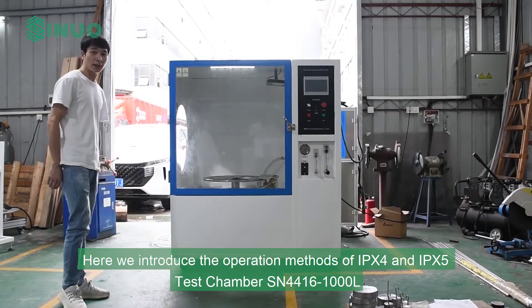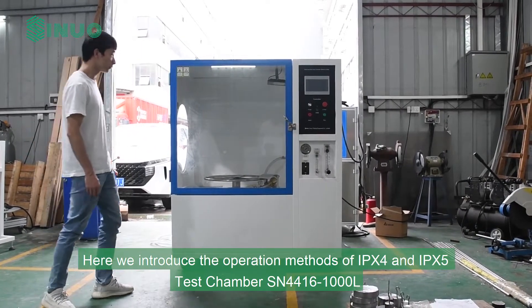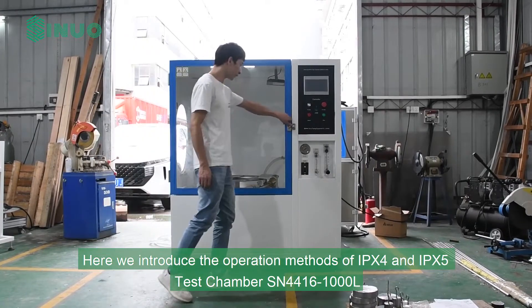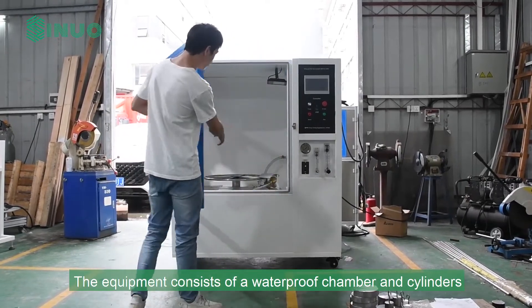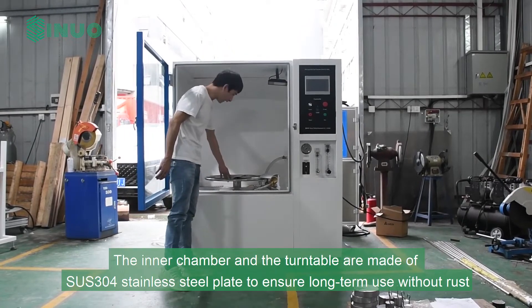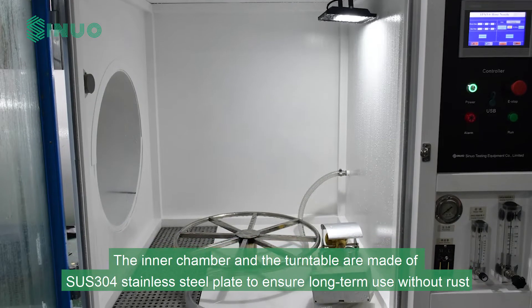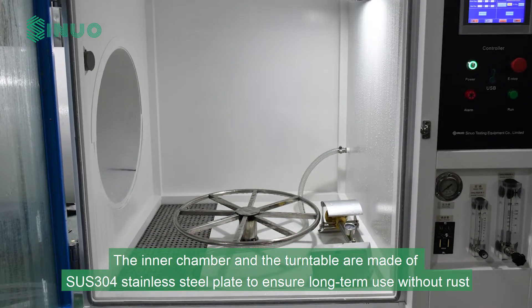Here we introduce the operation methods of IPX4 and IPX5 test chamber SN4416-1000L. The equipment consists of a waterproof chamber and cylinders. The inner chamber and the turntable are made of SUS304 stainless steel plate to ensure long-term use without rust.